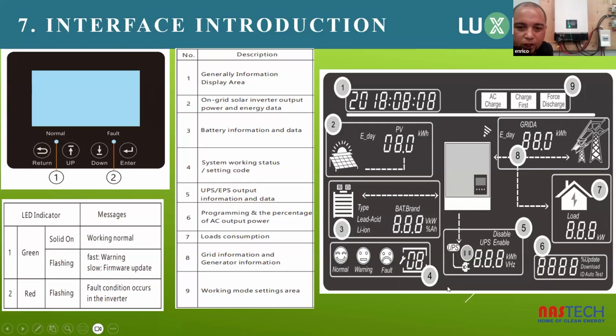Here at the bottom, in area 4, you will get your normal warning and your fault indicator. The inverter will tell you exactly what type of setup you have. You just have to look at your normal and your code that you get here in the corner. That code will tell you what type of setup you are running and whether the inverter is happy with that setup.